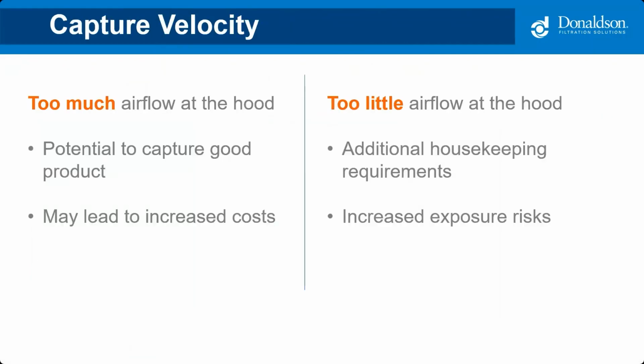Whether you're designing hoods or relying on machine design, we want to avoid airflow extremes. Too much airflow at the hood or pickup point may mean you're picking up good product rather than just nuisance dust. And since more energy is required to move more airflow, this could lead to higher than expected operational costs. Insufficient airflow at the hood could require additional housekeeping measures to be implemented, and depending on the dust, may lead to an increased risk of exposure.